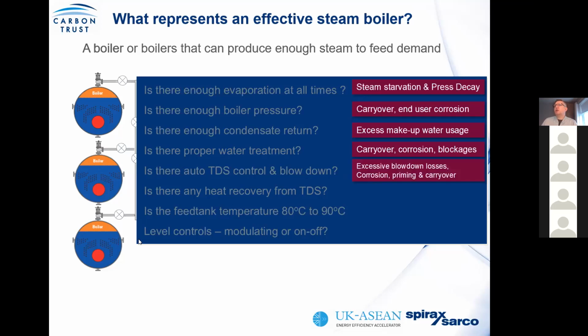Okay, is there auto TDS control and blowdown? Often we find that they're installed, but not working effectively. And where there's ineffective TDS control, you end up causing more issues with carryover. Is there heat recovery from TDS, where you have high TDS blowdown because of water quality? Are you recovering that energy? And again, we'll give a case example.